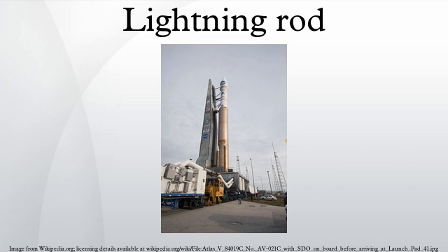To determine strike points, consider a sphere rolling over the terrain. At each point, we are simulating a potential leader position. Lightning is most likely to strike where the sphere touches the ground. Points that the sphere cannot roll across and touch are safest from lightning. Lightning protectors should be placed where they will prevent the sphere from touching a structure.